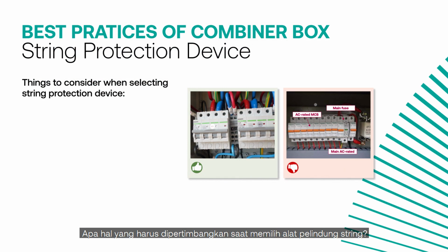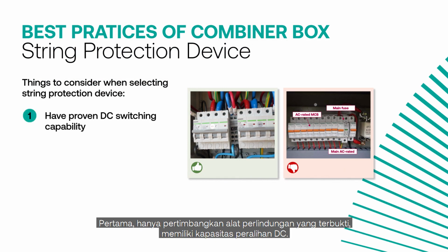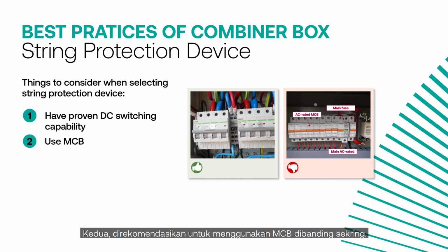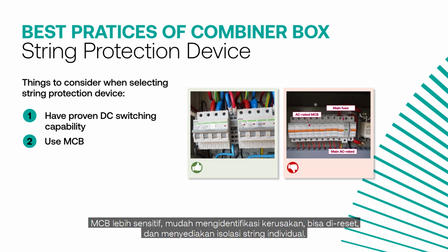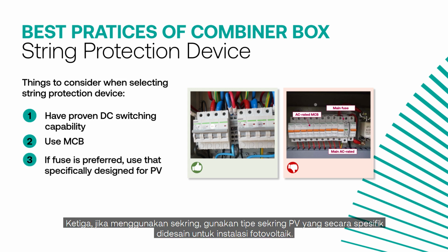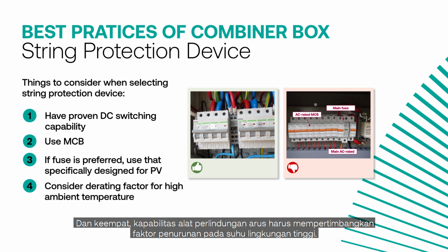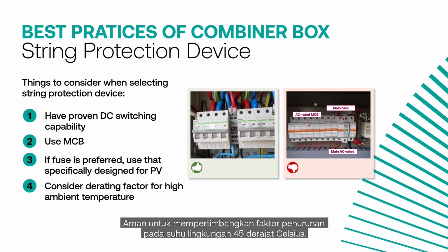What are things to consider when selecting a string protection device? First, only consider protection devices that have proven DC switching capability. Second, it is recommended to use MCBs rather than fuses. An MCB is more sensitive, easy to identify faults, able to be reset, safer, and also provides individual string isolation. Third, if a fuse is preferred, use a PV type of fuse specifically designed for photovoltaic installation. And fourth, the current capability of the protection device should consider the derating factor in case of high ambient temperature. It is safe to consider the derating factor at an ambient temperature of 45 degrees Celsius.